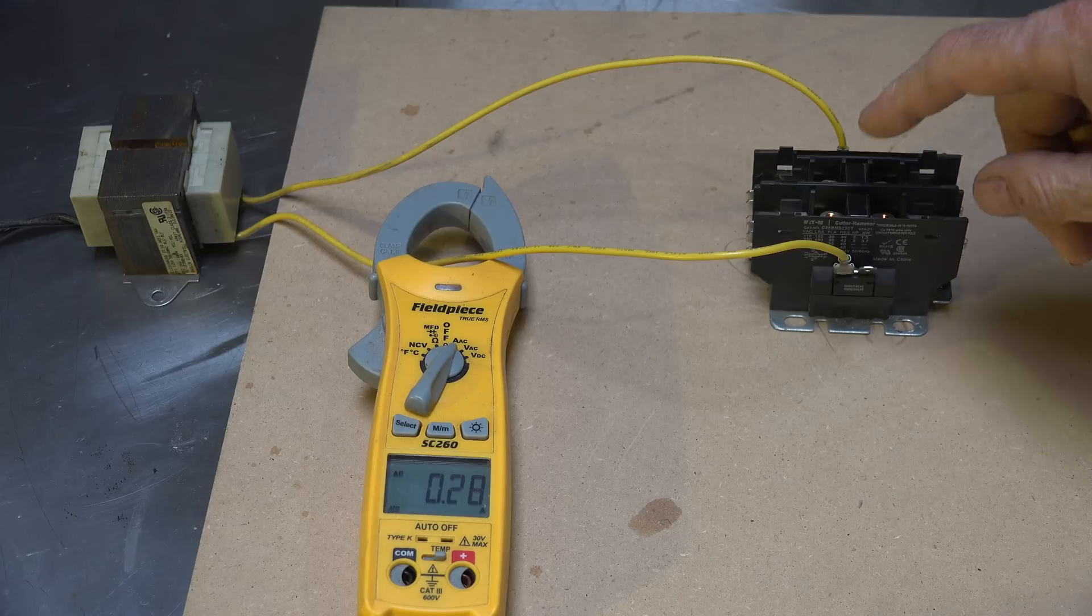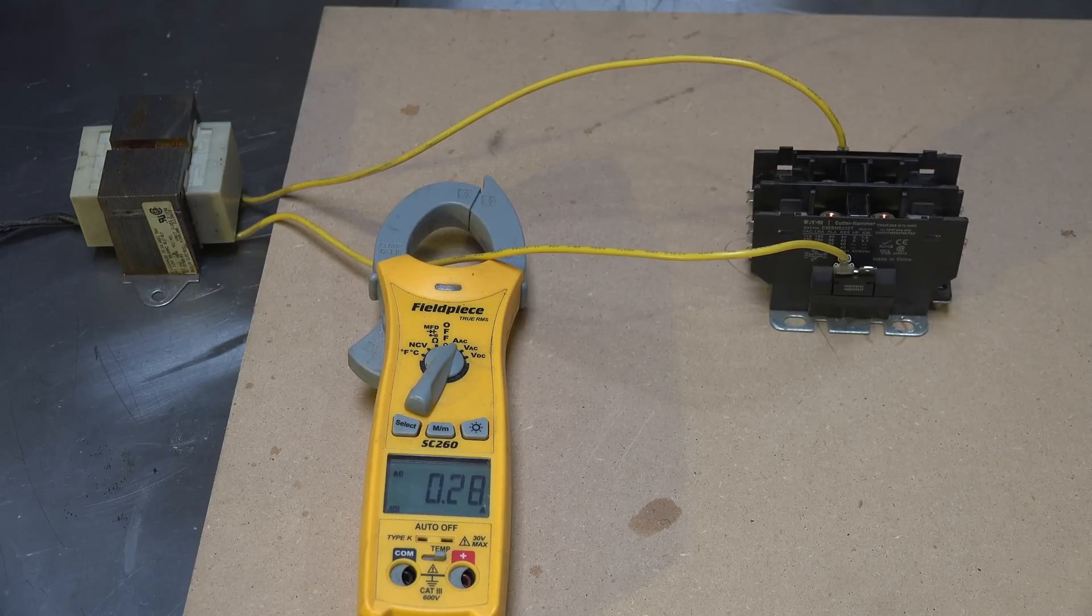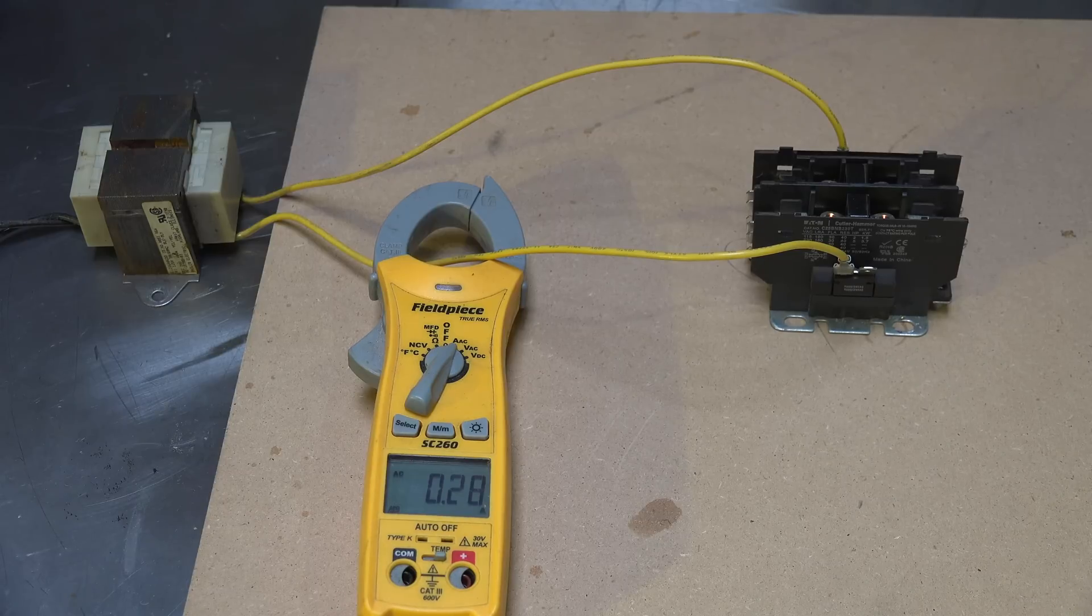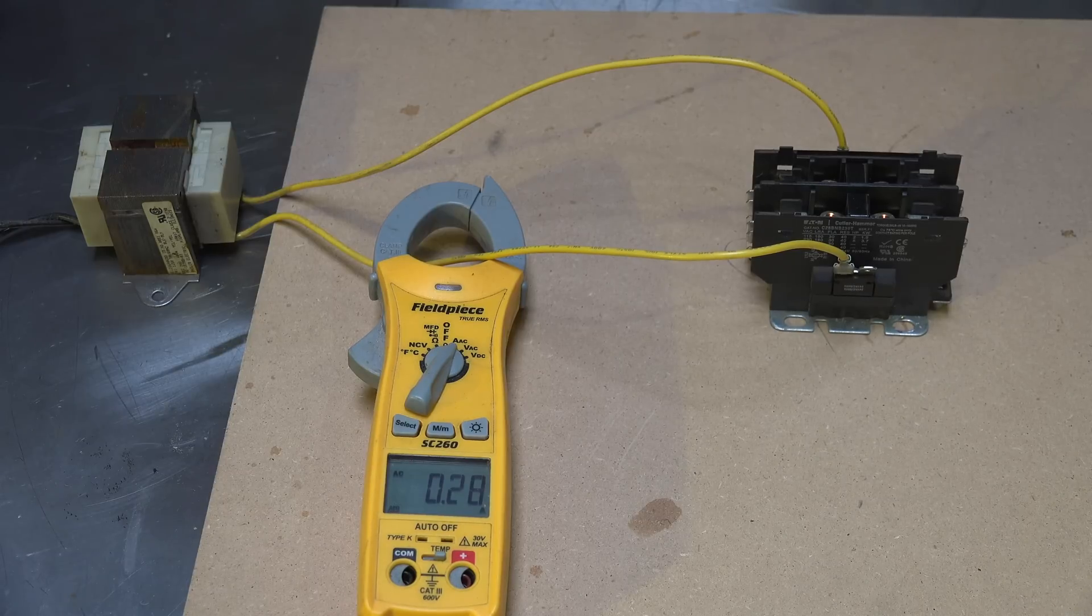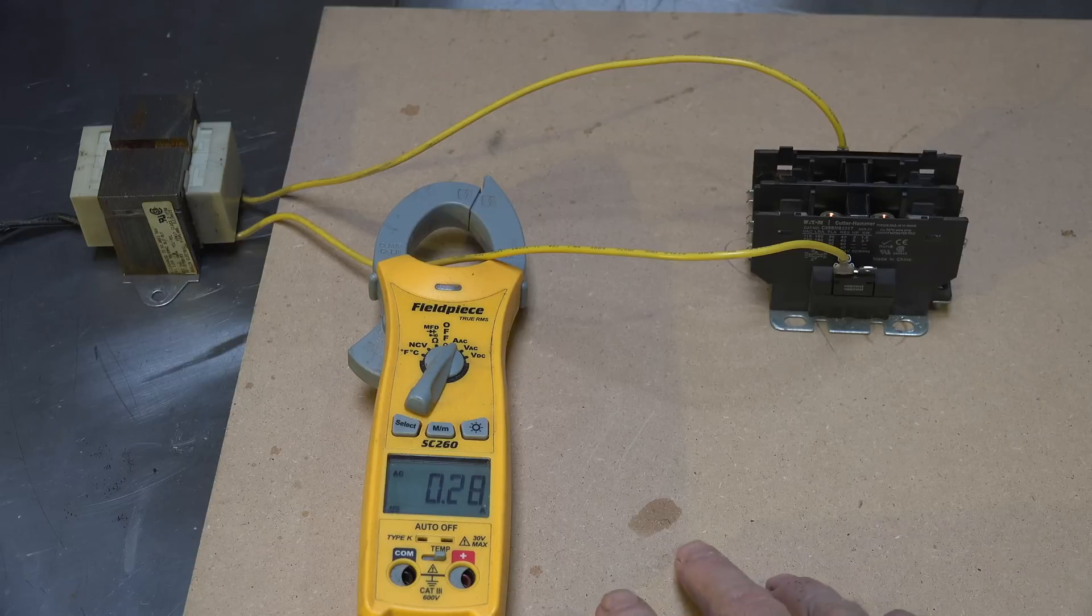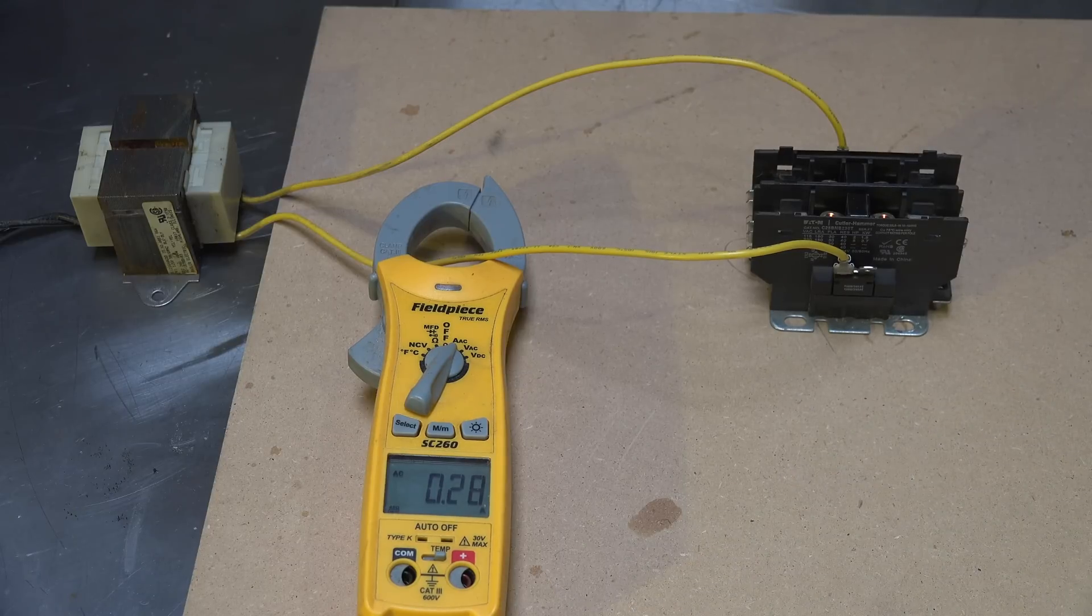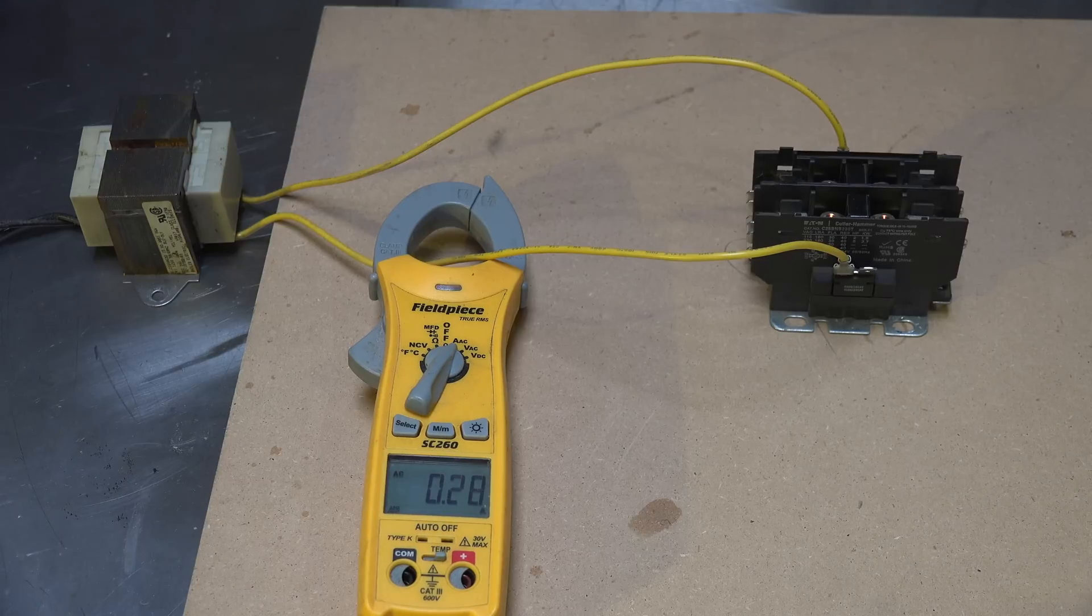Of course that'll burn the coil up on the contactor if it doesn't pull in, but why does it do that? Okay, right here I've got a contactor. I'm drawing 0.28 amps at 24 volts and it is pulled in. Now let's take this thing apart and see what happens.